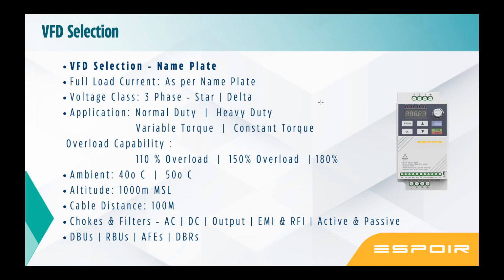So what you should do, how do you address this? You need to select one frame higher. Now, 50 degree, 45 degree, 11 kilowatt motor, if the ambient is going to be above 45 degree, you have to select a 15 kilowatt VFD, which will match the current rating as per the derating factor, which is very, very important. Then another aspect of selection is the altitude.